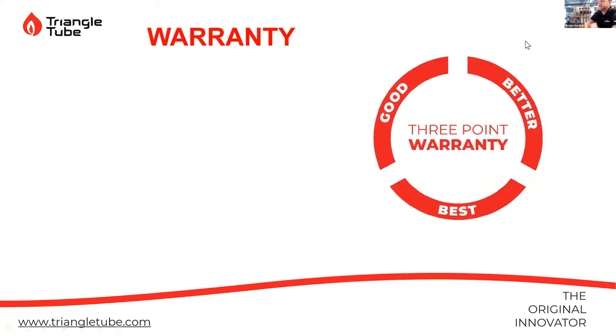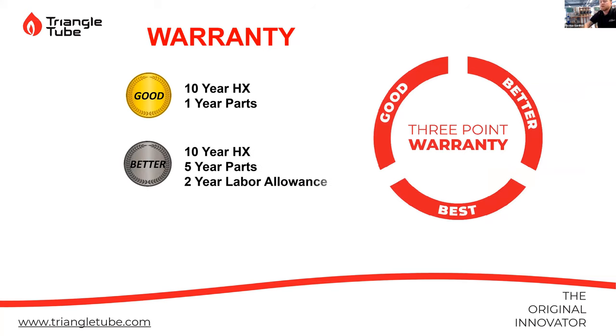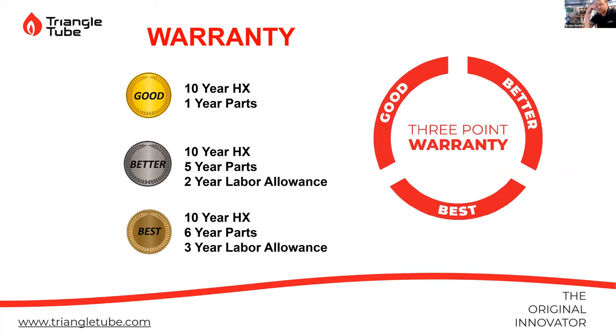And the warranty: good, better, best. Good is 10 years on the heat exchanger, 1 year on parts. Better is 10 years, 5 and 2. The best is 10, 6, and 3. So the whole thing with this is the registration. As long as you register that boiler and put your combustion settings in there, and I'll show you an analyzer I have that makes it really easy, you get this warranty, all right?